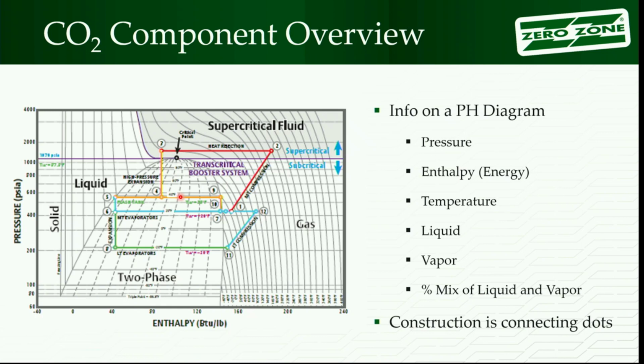You recompress it, you cool it, you recompress it and cool it. Which is why transcritical CO2 systems aren't so efficient, because you're kind of running this gas around the loop and not doing much with it. So if you want to get the most efficiency out of your system, you would always strive to have as much liquid as possible. You don't want to have gas. You don't want to have gas coming out of it.